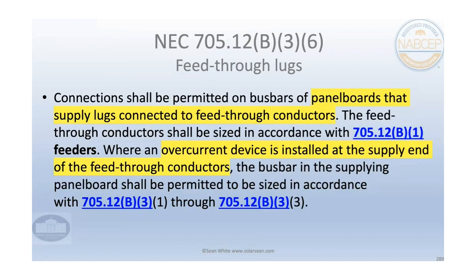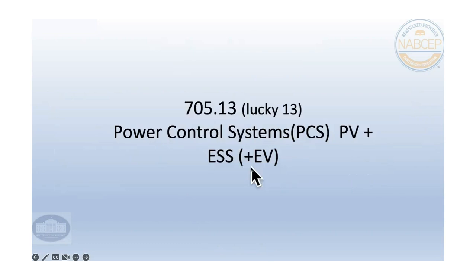And then there's feed through lugs. What we have here is sometimes bus bars, at the bottom of the bus bar, say the main breaker's at the top, at the bottom, they have lugs right to the bus bar. And you can connect a conductor to that, and it's sort of like an extension of the bus bar. That's the way that I look at it. We don't see a whole lot of that, but you might need to put an overcurrent protection device at the bottom of those lugs in order to get it to do more things that way.